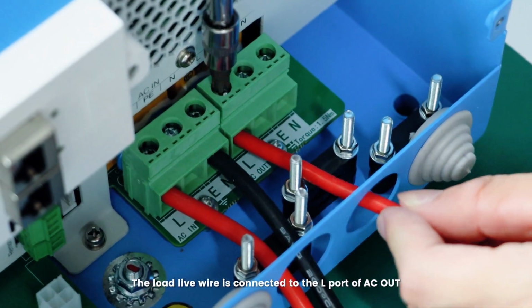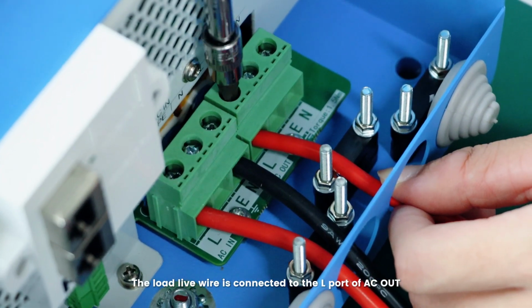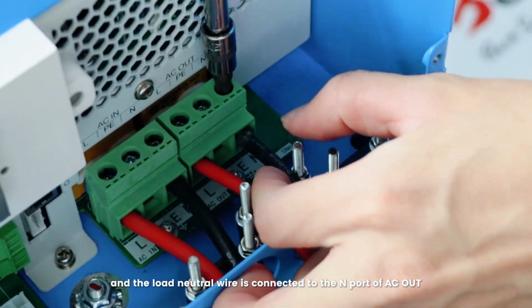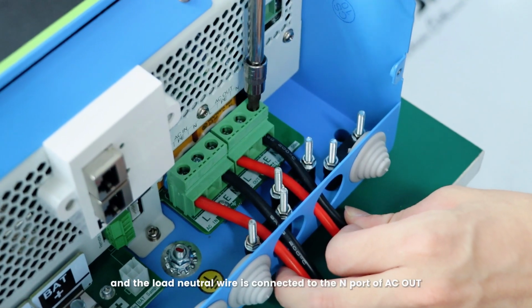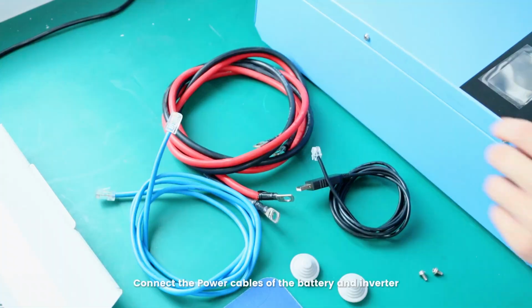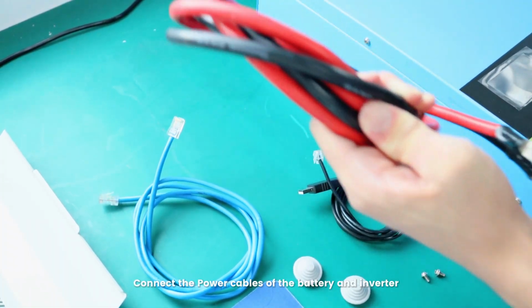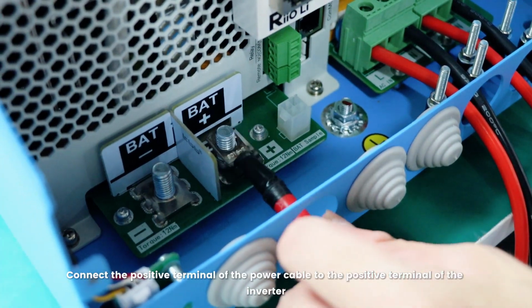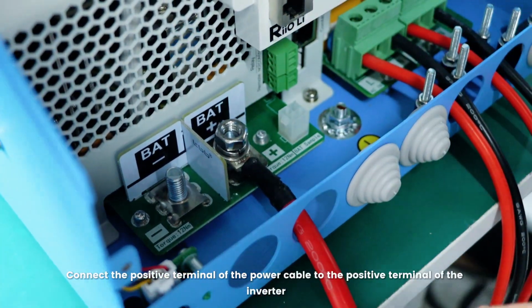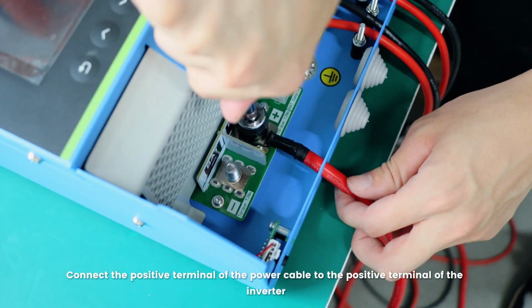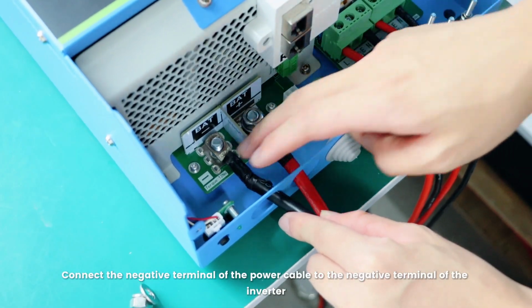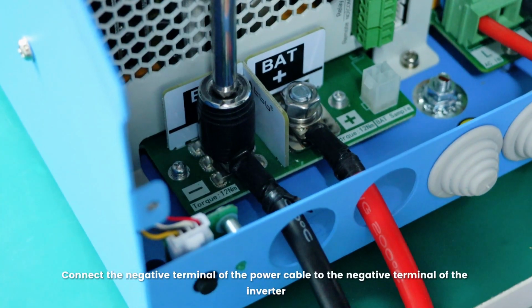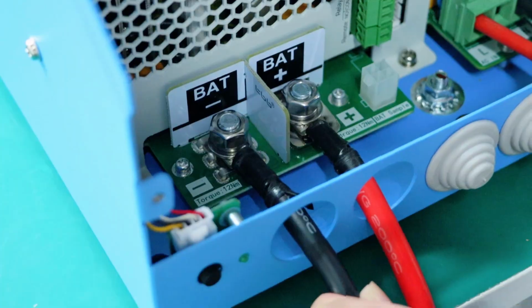The load live wire is connected to the L port of AC out, and the load neutral wire is connected to the N port of AC out. Connect the power cables of the battery and inverter. Connect the positive terminal of the power cable to the positive terminal of the inverter. Connect the negative terminal of the power cable to the negative terminal of the inverter.